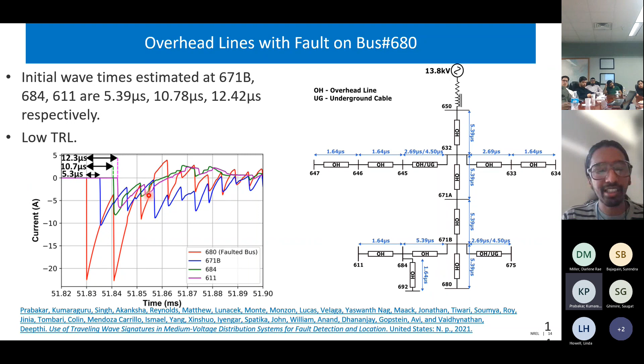So we had to go to actual experiments, using power hardware. We had to use real world overhead lines and underground cables, actual faults, actual bolted faults, and actual CTs, current transformers, that can capture wide frequency data and show this in a field experiment. We also had to show that we can differentiate between noise and the high frequency traveling waves. If we could successfully do it, you can consider this mid to high TRL, going beyond breadboard and closer to what the paper calls the relevant environment.